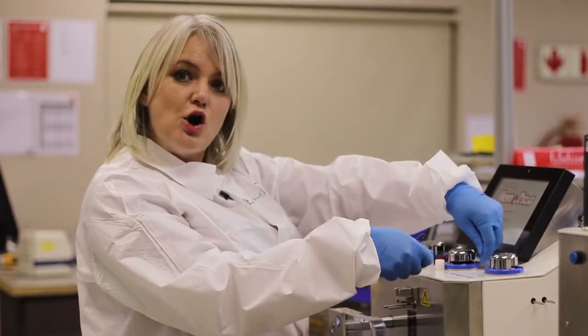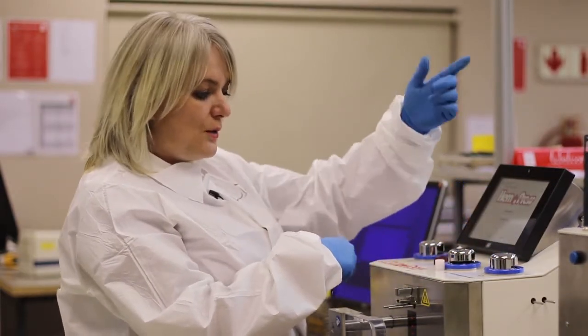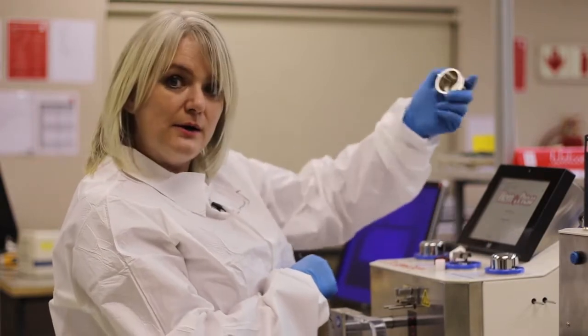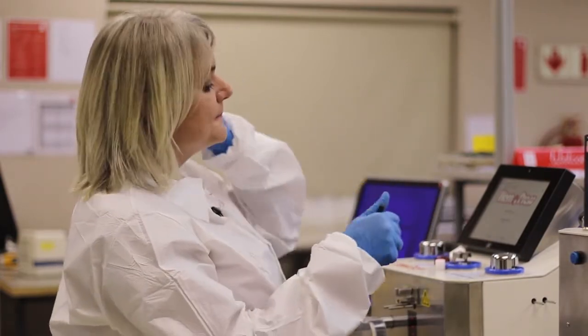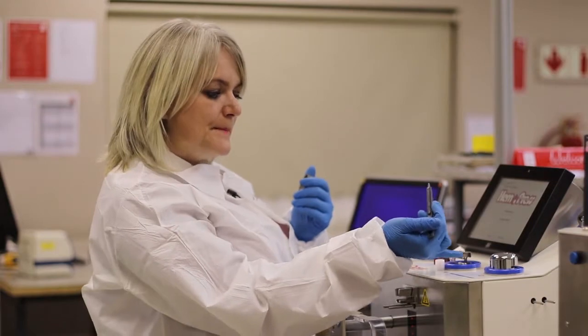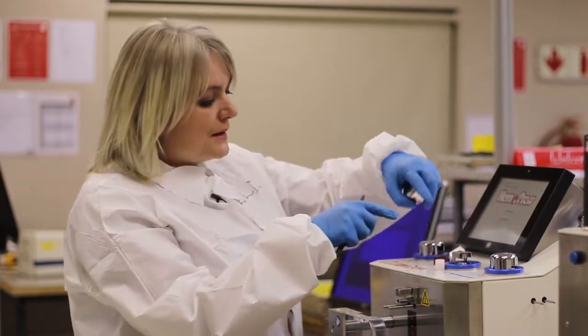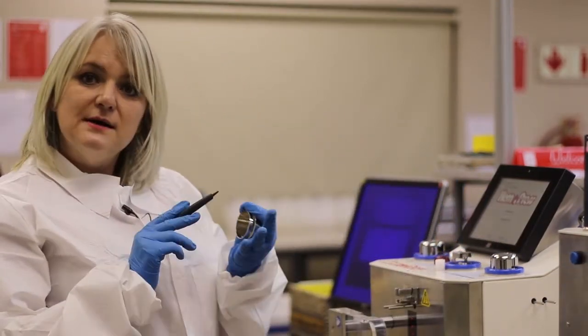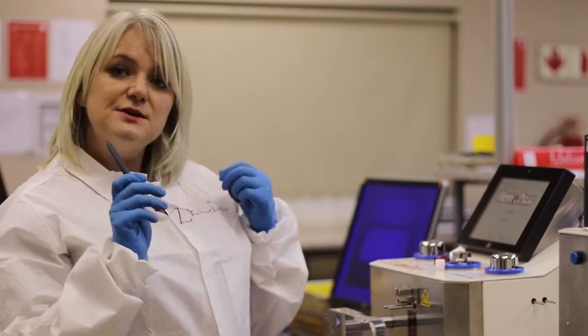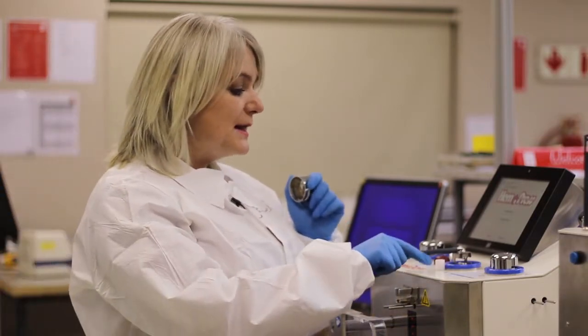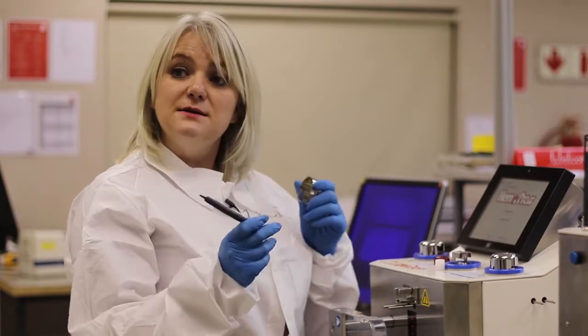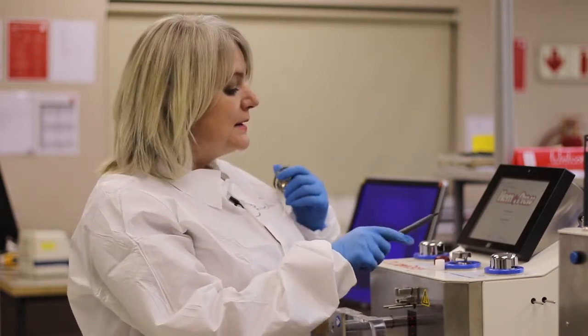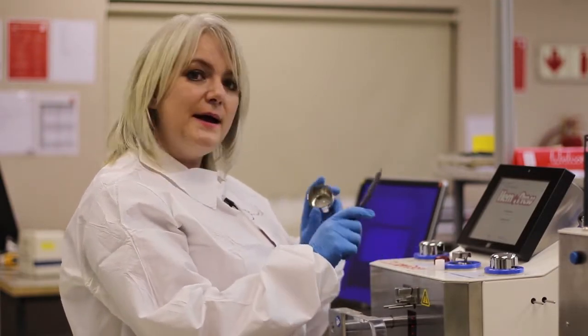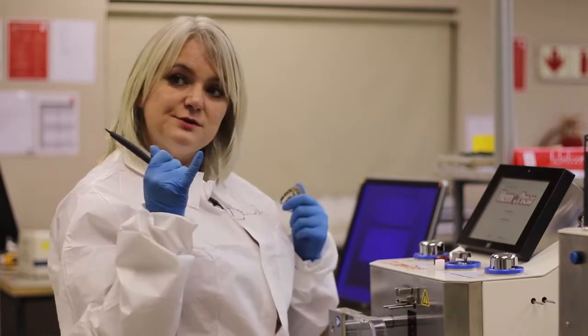Solenoid clamps, we load the tubing from the side. I will demonstrate a bit more on that when we load one onto a machine. So your tubing will be slid into the clamp. The clamp has got 3 purposes. The first one will be as a tube detector. When you do your initialization, the machine will alert you. The clamp will make an alarm if there isn't a tubing in the clamp. So it will alert you and say clamp A, no tubing. That's the first function of the clamp.